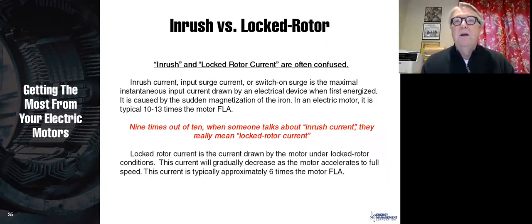Now, there is a difference between inrush and locked rotor, and I don't get too bent on this, but most of the time when people talk about inrush, they're not really meaning inrush, they're meaning locked rotor current. So what is the difference? Well, when you energize a transformer, you get about, let's just say, 10 times current. That's the current that goes in to magnetize the iron in the transformer. Well, a motor is just a rotating transformer. And when you first energize the motor, you're going to get 10, 11, 12, 13 times current for less than half a cycle, in order just to magnetize the iron. Now, as soon as the iron is magnetized, the current drops from, let's say, 13 times down to about 6 times, and that becomes your locked rotor current.